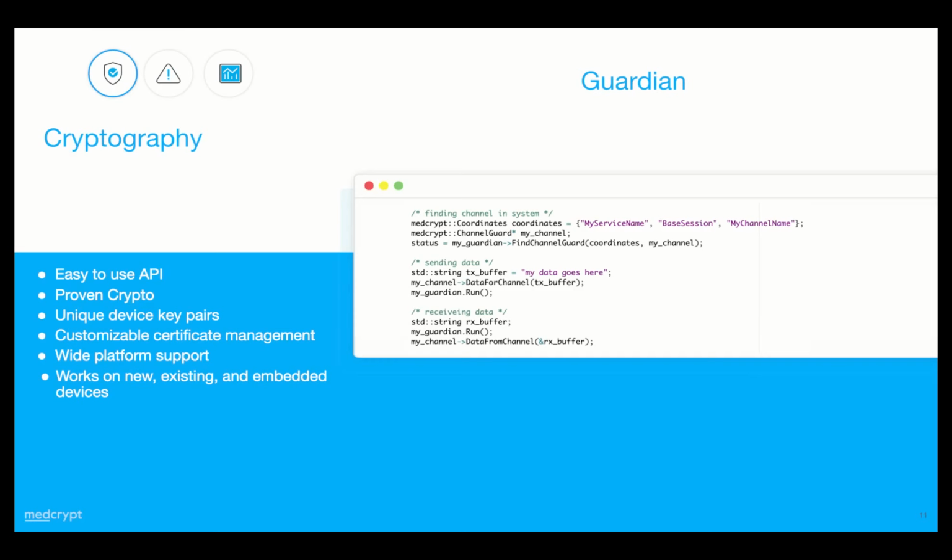This is critically important, particularly when you think about something like a surgical robot. The last thing you want to do is have a security feature in the middle of an operation turn off that robot or make something inaccessible. So we want to always maintain that clinical functionality at all costs, and that's why we allow the MDM to choose those parameters going forward.